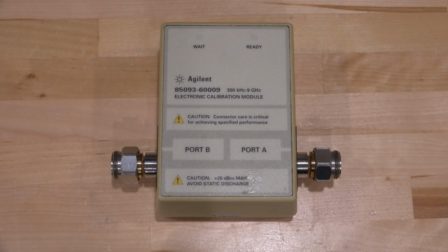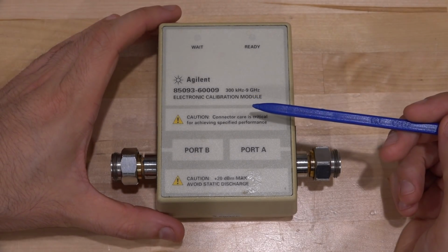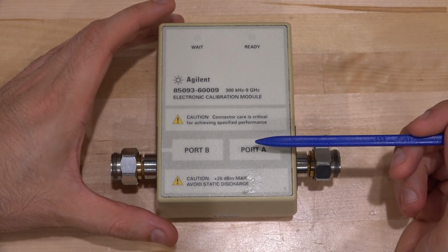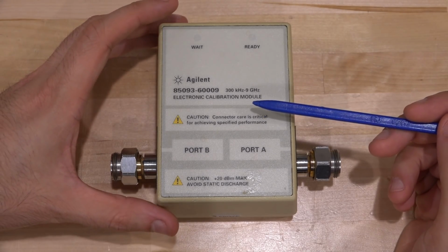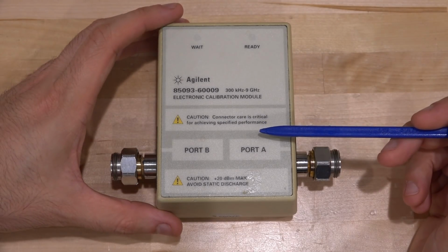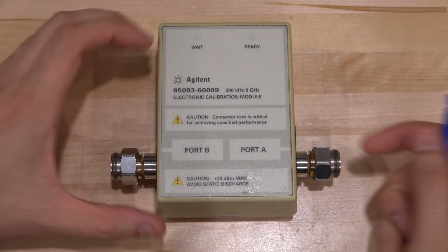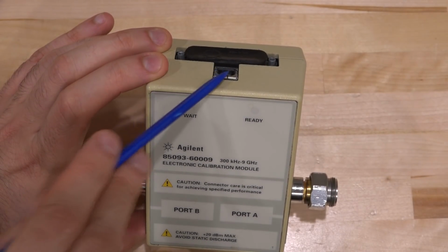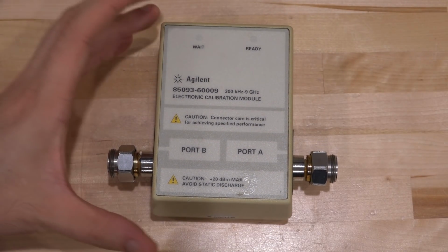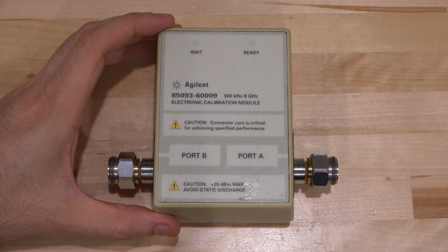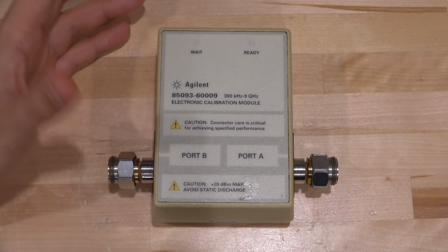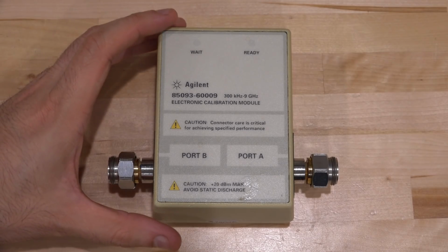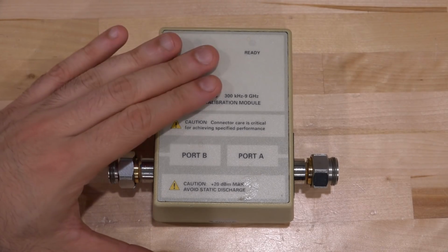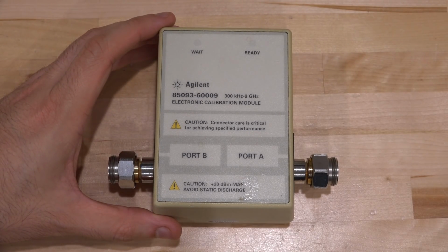In this episode, we're going to take a look at another viewer-sent item. This is an Agilent Electronic Calibration Module. This one is up to 9 gigahertz. It's actually not a very high frequency one. You can now get these things almost to 100 gigahertz. It's a 2-port version. It still has the old connector at the top, but it does have USB, of course. So what you do with this is you just simply connect the USB port directly to your network analyzer. The instrument will recognize this, download the information from what is on the EEPROM of this one, and then you can then perform your calibration.